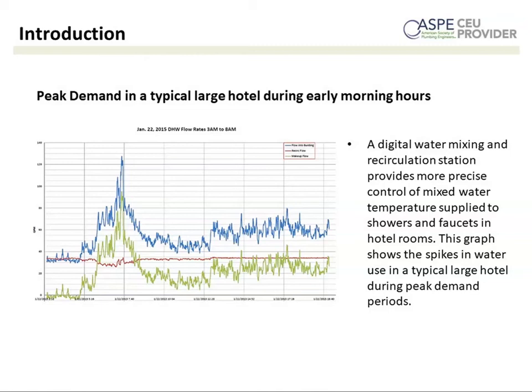Digital mixing valves help mitigate some of that issue, but clearly you want your valve or your valve system to be sized properly. And there are programs that we'll talk about a little bit later that help you do that. But in most cases, what we find, and this was a fairly large hotel that had flow sensors on it, and this is like a 500-plus room hotel.